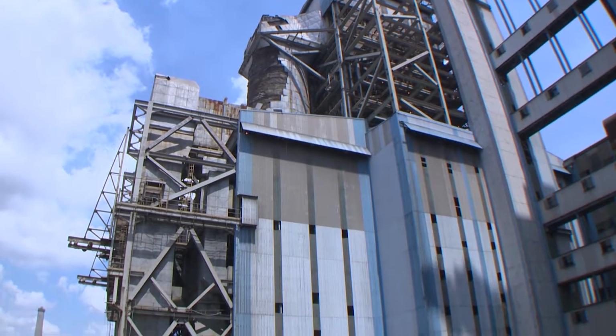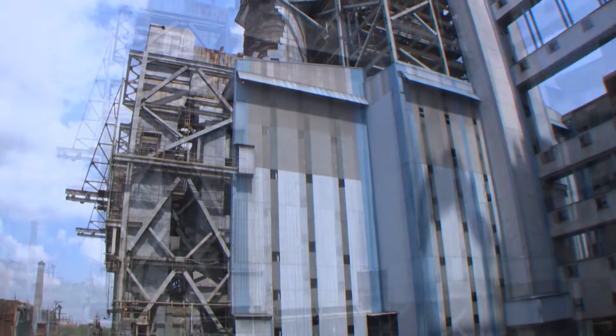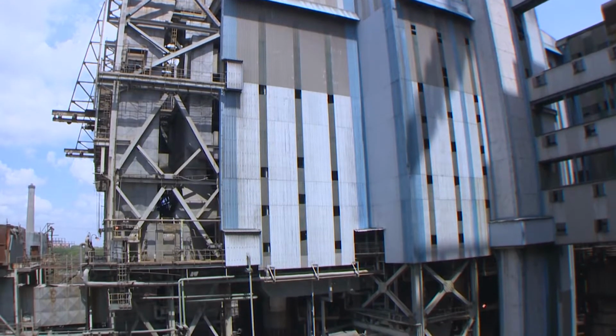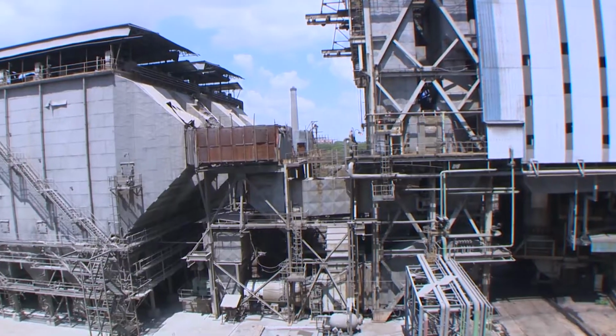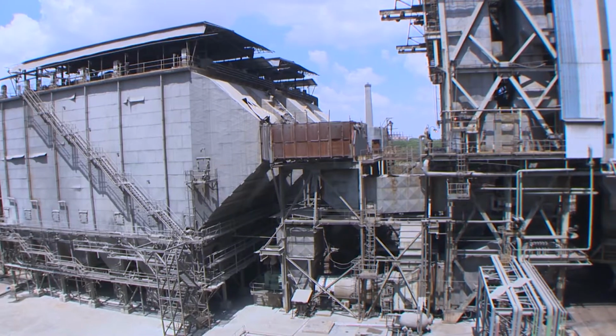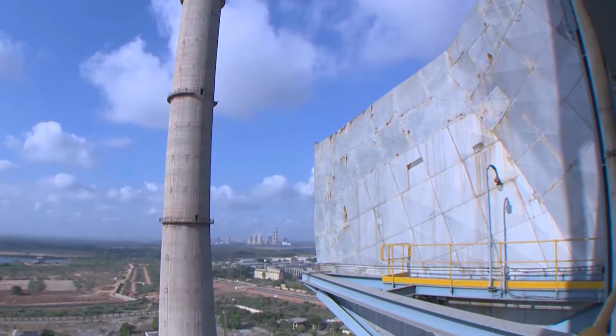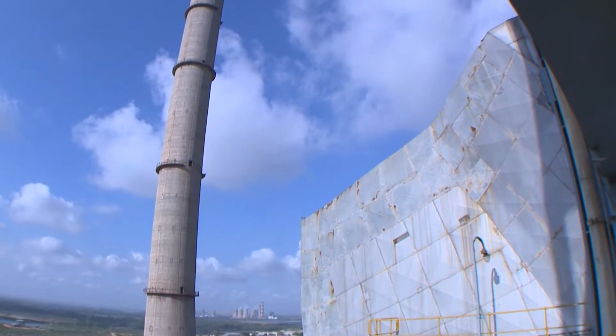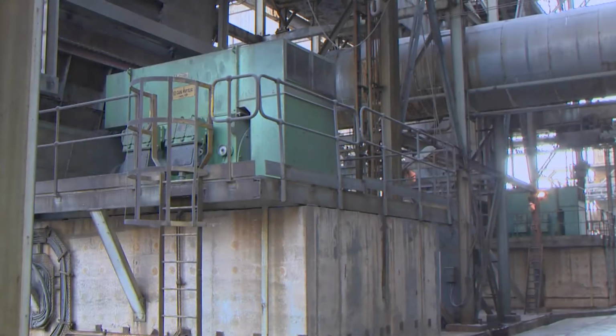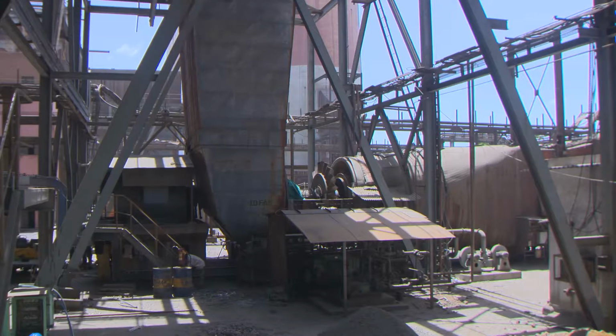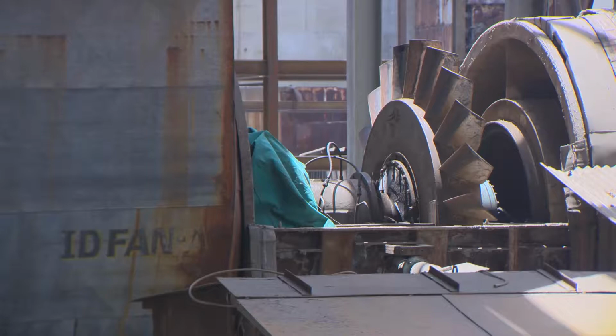The induced draft fan sucks hot flue gas from the furnace through the regenerative air preheater and electrostatic precipitator, then lets out the same to the atmosphere through the chimney. The induced draft fans are also axial flow variable blade pitch control type.